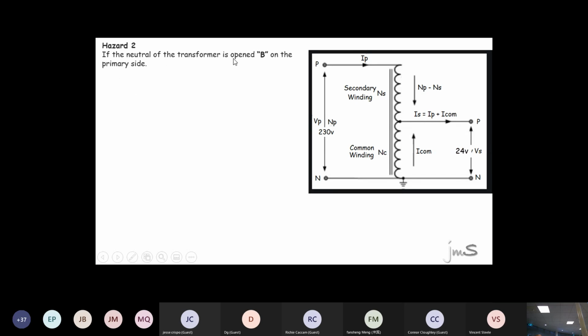If the neutral of the transformer is open at B - where's B? There. If you break that neutral, what is the hazard? See that voltage there? It goes to 0 volts. But the problem is, what's the potential voltage between that P and the earth? Still 230 volts. So that's very important - there's still a potential hazard of 230 volts on that transformer. That's a very hard one to understand. If you break the neutral or you break the coil, it's now simple - everything becomes supply voltage. How's that sound?